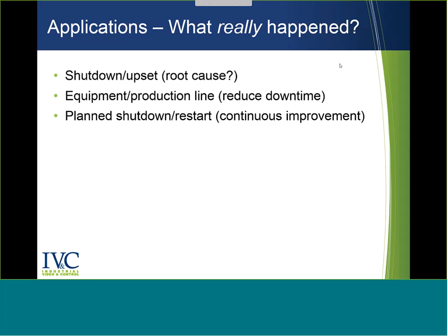For troubleshooting, the scenario I hear the most is: my operator said he didn't get the alarm, that's why he didn't acknowledge it, and I can't tell if he did or didn't. The HMI says it was there, but he's saying he didn't see it. So you'll be able to go back in time by just clicking on that alarm, and it'll bring up the operator screen exactly at the time when the alarm occurred.